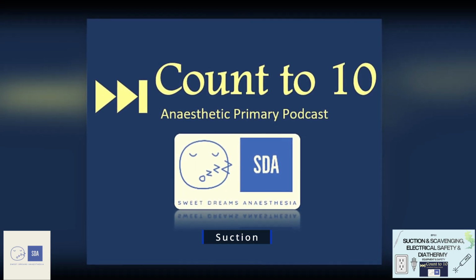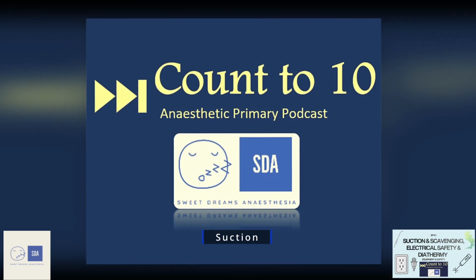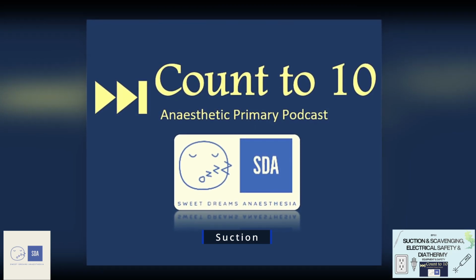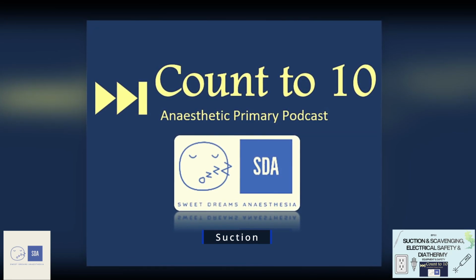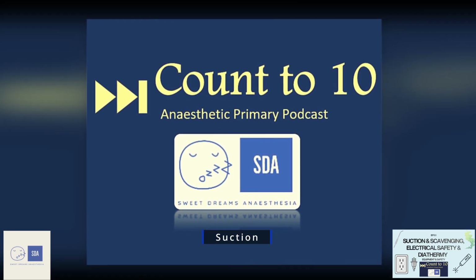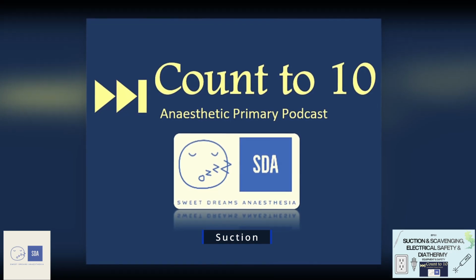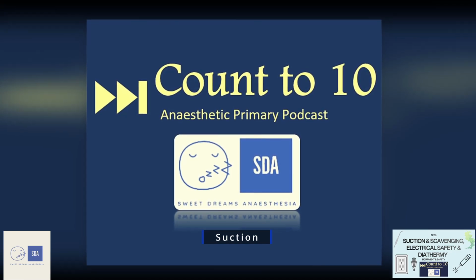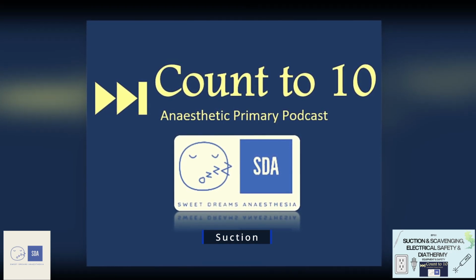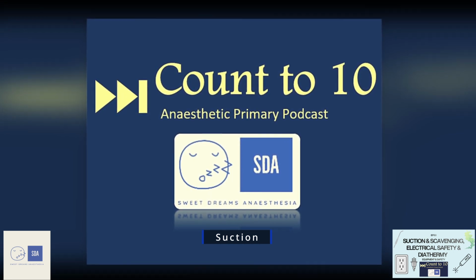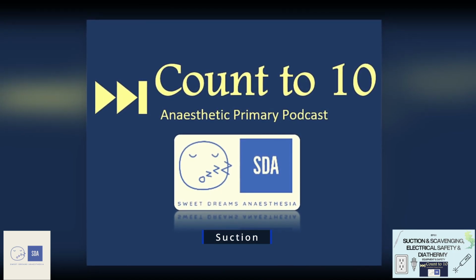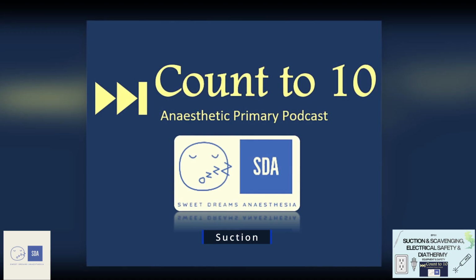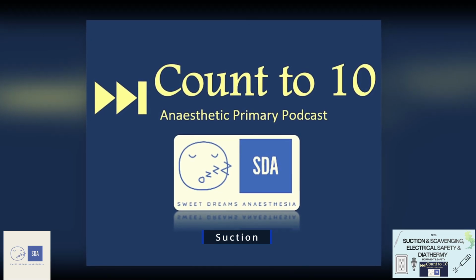There's nothing fancy about the Yankauer or the flexible sucker. The key thing again is that you want to make the device safe enough that it doesn't collapse within its own negative pressure, and within the flexible sucker, it has a safety feature. As you might note, it has a little aperture on the side which exposes it to room air. This is there so that you're not constantly putting a high degree of negative pressure at the end tip of that catheter, because as you're blindly poking that into, say, a little baby, that can be a huge area of negative pressure that can create trauma.